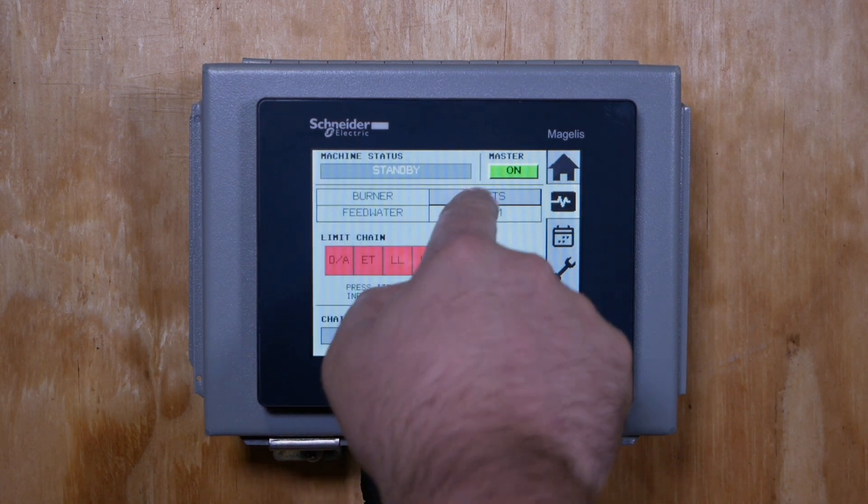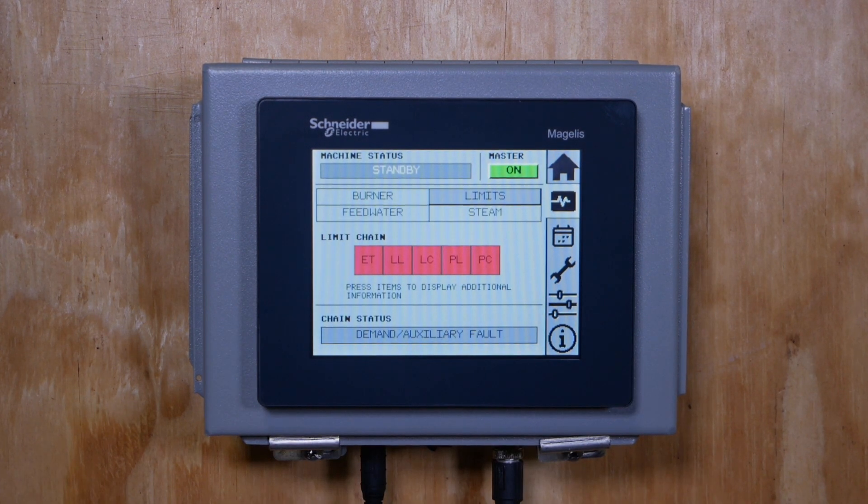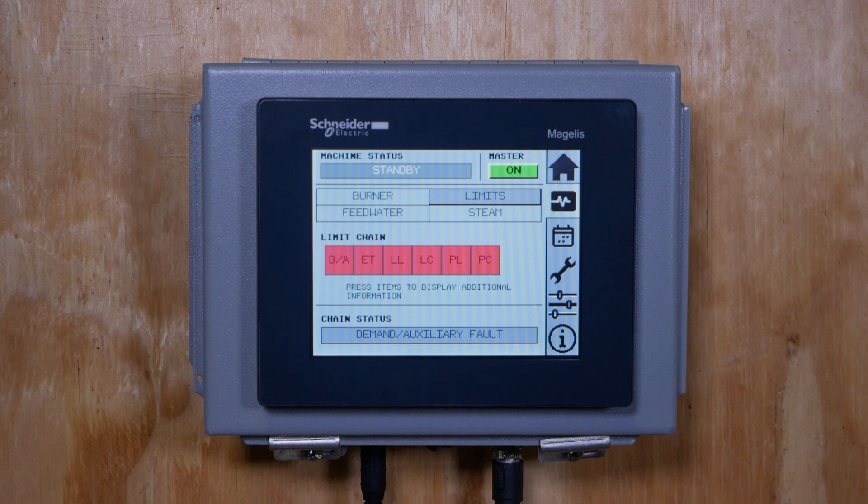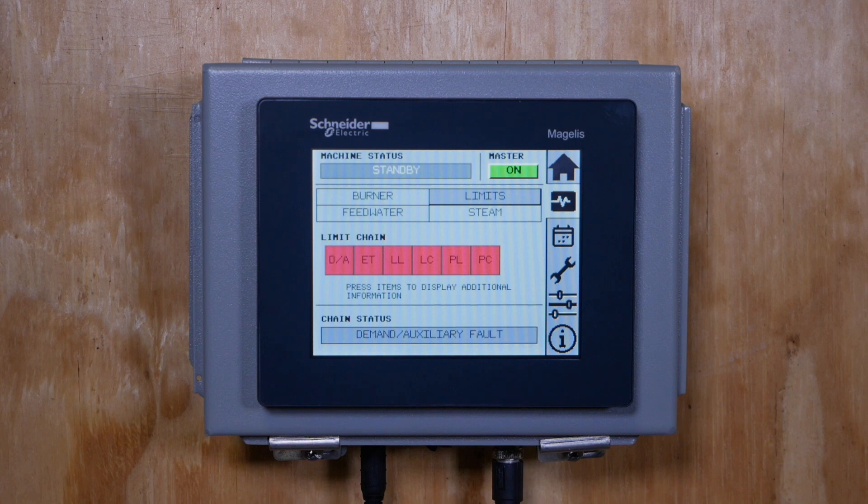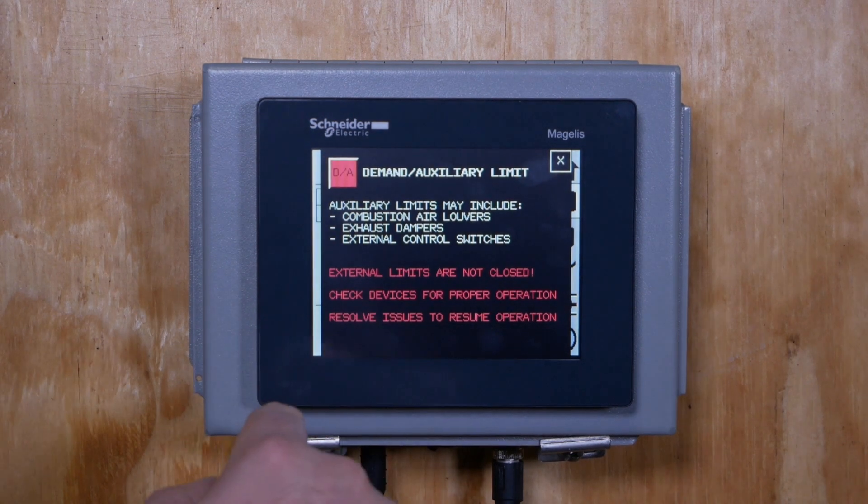The limit page displays the safety limit chain. This is a digital representation of all safety controls on the steam generator. If the control has power, it is displayed green. If the control does not have power, it is displayed red. A flashing red indicator pinpoints where the limit chain is broken. Each safety device indicator can be tapped for additional information.